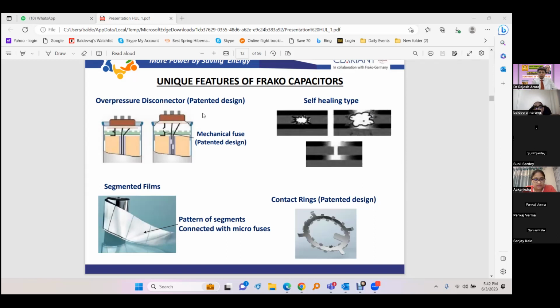Another feature is the segmented film today. If there is a fault, it remains only in that segment and doesn't travel throughout the film and fail the entire capacitor. Then there is the contact ring for the end connections, which makes this protection work effectively, and there is no loss of MFD because no soldering is involved. These protections are available in MPP and not in APP capacitors. Another thing is that when this capacitor fails, it fails in open circuit mode. It totally isolates itself and does not remain in the circuit.